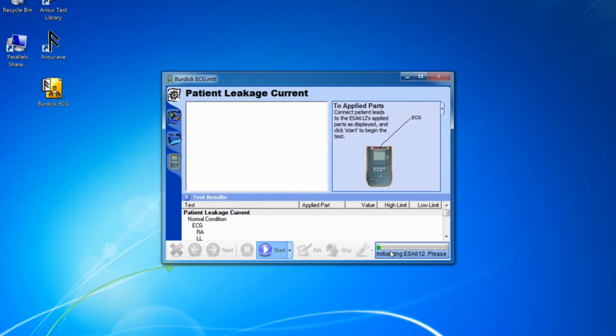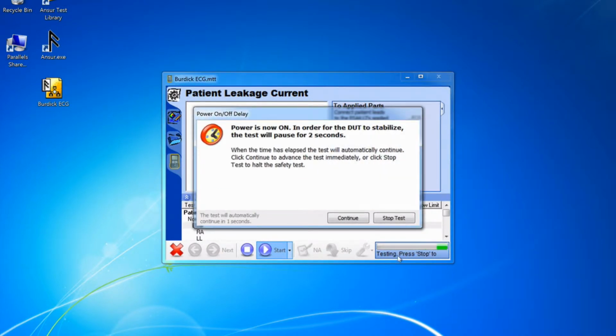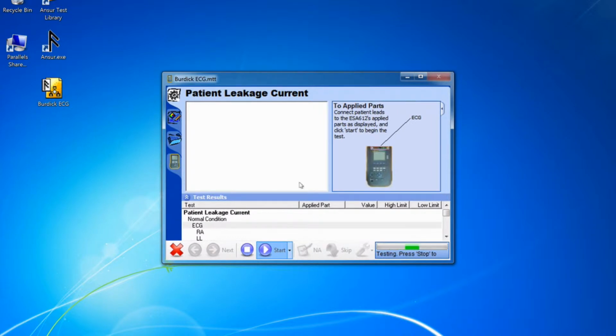It shows here that it's communicating with the safety analyzer. You will have some pop-ups from time to time, but they automatically close. The values we're looking for: the high limit for leakage current is 10 microamps. So anything less than 10 microamps is good. And we're just going to let the test proceed. It takes a few minutes.